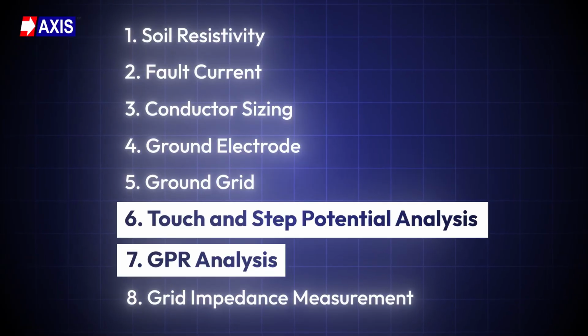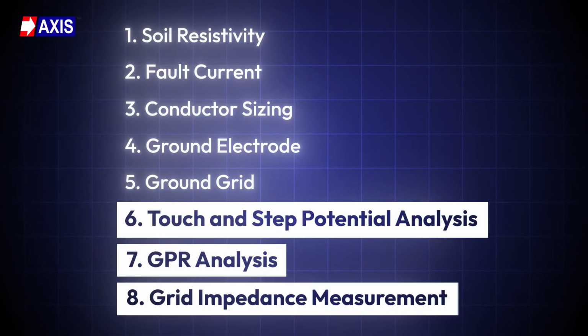These electrodes are then interconnected across the substation to form the ground grid, which is the physical backbone of the entire earthing system. With the ground grid in place, the design moves into analysis, steps 6, 7, and 8, which involve touch and step potential analysis, ground potential rise analysis, and grid impedance measurement. We've already covered each of these in detail in the risk section of this video, so you can watch it back there if you want to refresh yourself.